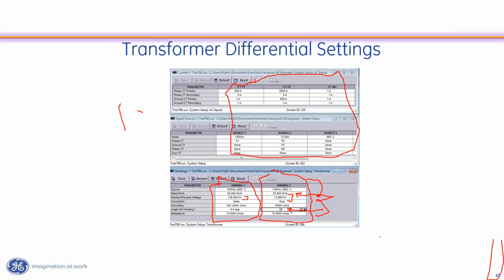Okay, let me find my pen again. There's my pen. And then this other setting right here, this within zone, basically that's saying, is there a ground source inside of that protective zone, inside of the CTs? Because our differential zone of protection is from the high side to the low side CTs. So in this case, it looks like my 13.8 kV side is wired in Y, so it has a ground source, which means it's solidly grounded inside of the zone of protection, so I set that to within zone.